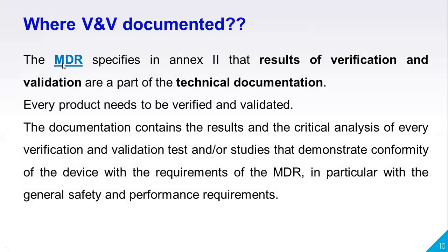So the MDR specified, MDR means medical device regulation. The medical device regulation specifies in Annex 2, there are two annexes, particularly the technical documentation entirely related to Annex 2. So the MDR specifies in Annex 2 that the results of verification and validation are a part of the technical documentation, that is STED. We already learned, right? Summary of technical documentation.